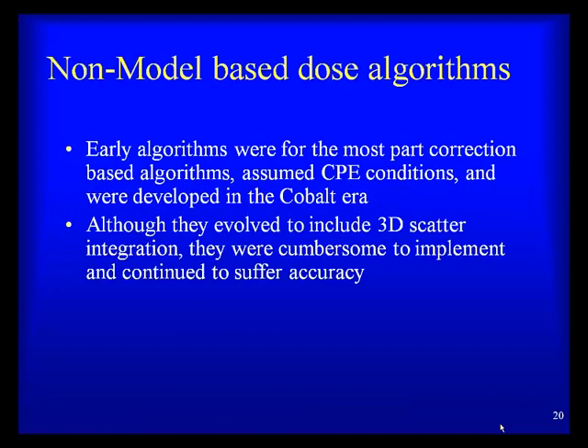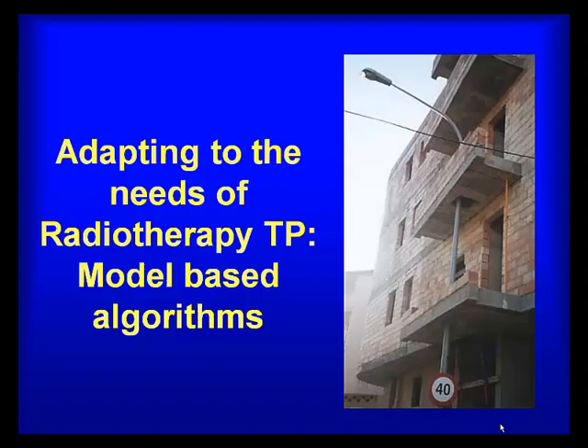In summary, the early non-model-based algorithms were mostly correction-based methods using effective path length, assuming charged particle electronic equilibrium, and were developed in the cobalt era at 1.25 MeV photon energies. Although they evolved to include 3D scatter integration like ETAR, they were cumbersome to implement and continued to suffer accuracy issues for more complex applications such as IMRT. This drove the development of the new generation of model-based algorithms.